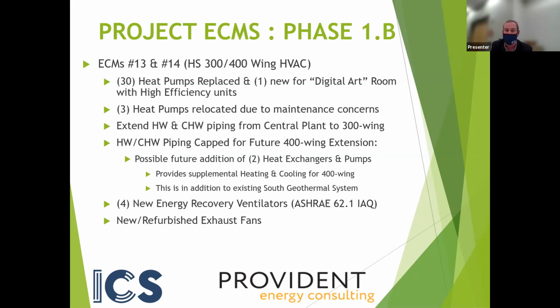We're also extending the hot water and chill water piping from the central plant to the 300 wing to refeed an air handling unit and reheats in those areas. We've sized that line for both the 300 and 400 wing to provide redundancy if needed in the future. However, based on the geothermal study and the load reduction already achieved, it's not required that you install the two heat exchangers and sets of pumps for supplemental heating and cooling, which was the original plan back in November. After our analysis, we feel this isn't necessary and would be a considerable added cost—certainly an option if you'd like, but we don't think it's needed at this point.